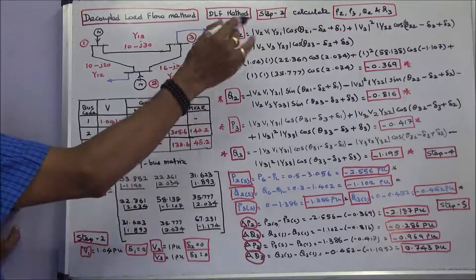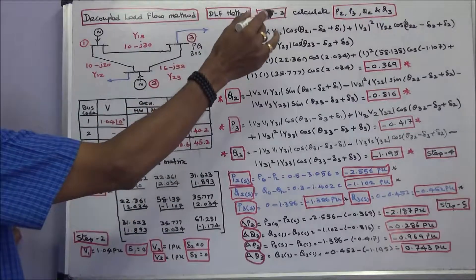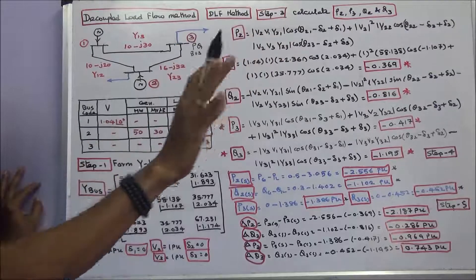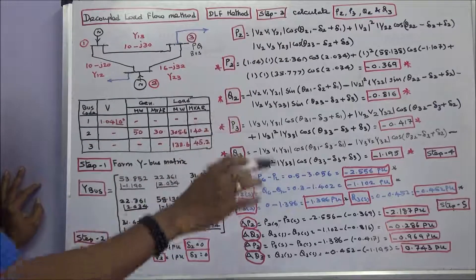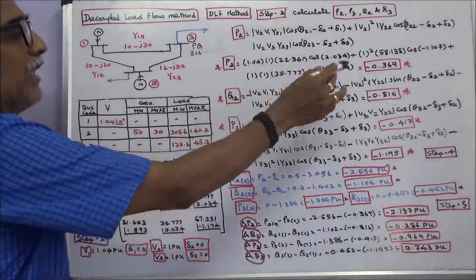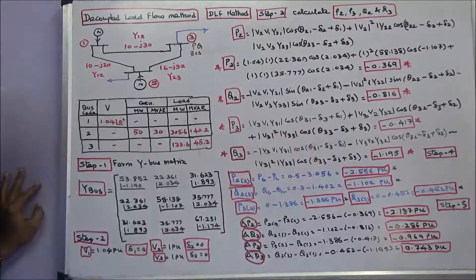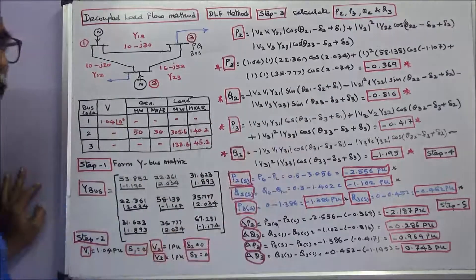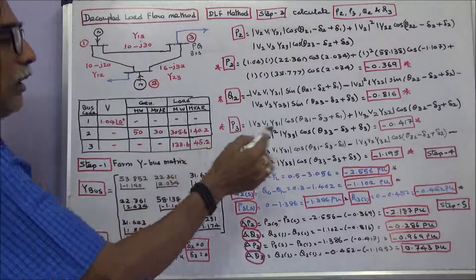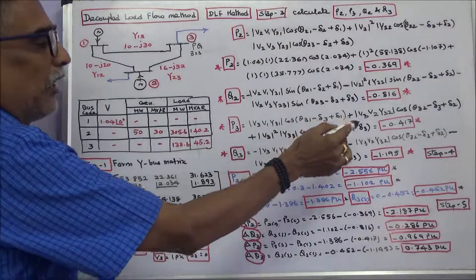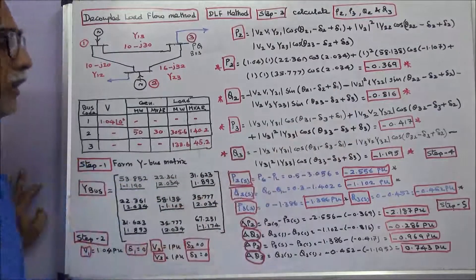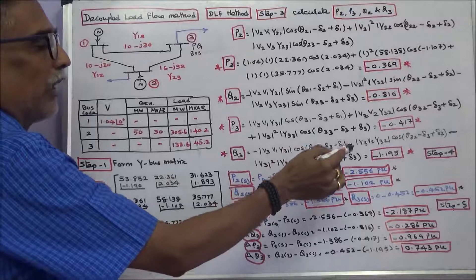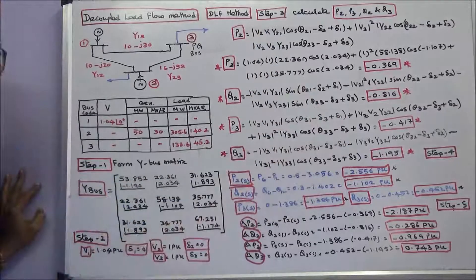Step 3: Calculate P2, P3, Q2, Q3 using the static load flow equations. P2 = -0.369 per unit, Q2 = -0.816 per unit, P3 = -0.417 per unit, Q3 = -1.195 per unit — all are in per unit.